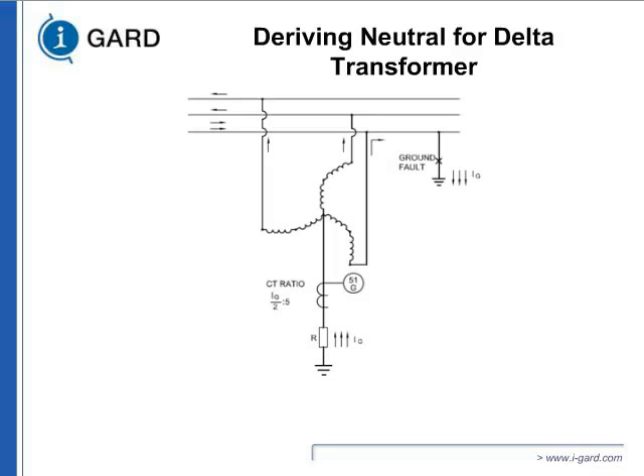You can see that you have a delta, you put a zigzag transformer, or some places you put two winding transformers, and you detect when the ground is there. It doesn't tell you where the ground is, it doesn't tell you how to locate it, but it does give you an option to detect the ground on the delta. People who are familiar with 60s and 70s design, and if they're nodding their head, they would have that at their site even currently, because transformers, you do not change that frequently.